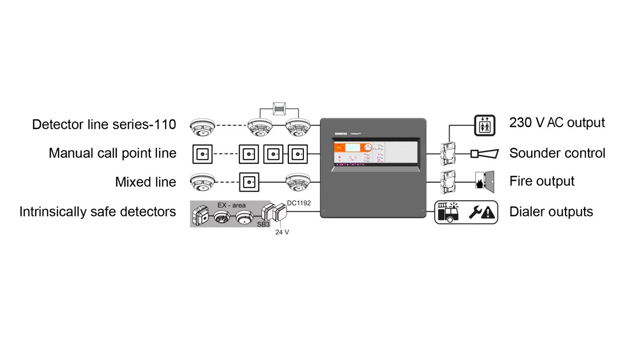The Siemens FC20 is a conventional fire control system that includes all the components required for the detection and setting off the alarm in the event of a fire. The integrated operating unit processes signals from the conventional and collective detectors. You can see this on the left side of the picture. You can connect conventional detectors like Siemens 110 series, conventional manual call points, or other conventional equipment like detectors for explosive environment. On the right side, you can see the possible outputs triggered in case of an alarm. These could be 230-volt standard outputs, special lines for sounders, and connection to routing equipment.